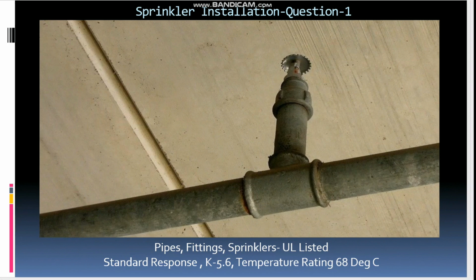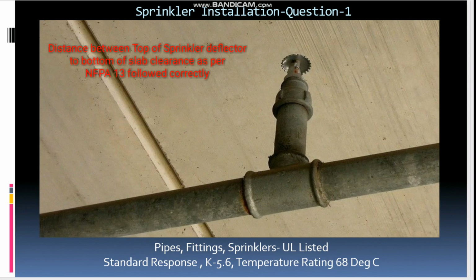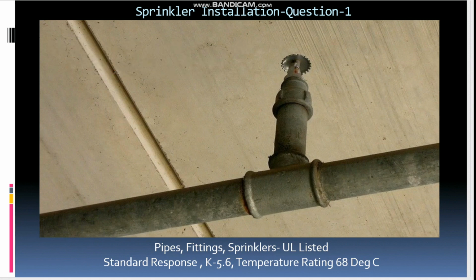So what you see here is the pipes, fittings, sprinklers, all are UL listed, and the sprinklers are standard response. It has the K factor 5.6, temperature rating 68 degrees Celsius. So all these things are approved as per the material submittal and proper documents we have. So coming to the installation, there is an issue in this installation. This installation will affect the performance of the sprinkler. The answer for this question I will explain later with the proper subject of NFPA.